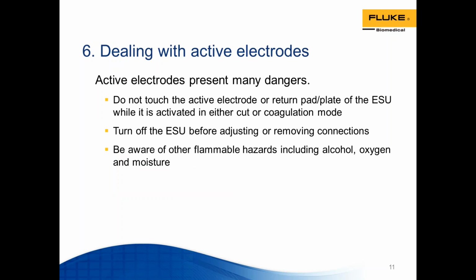Number 6, dealing with active electrodes. Most of us for many, many, many years have been improvising connections in order to run the tests on electrosurgery units. And that means we use alligator clips and we try and use the disposable pencil with the hand controls, and it's just dangerous. The reason is because you could touch by accident the active electrode or the return plate of the ESU while the ESU is activated in either cut or coag mode. That's going to cause a current to flow through you, and you really don't want that. That could result in burns to yourself at minimum.